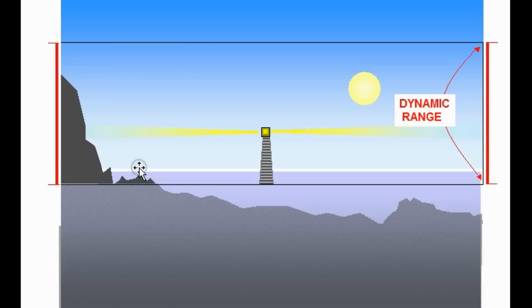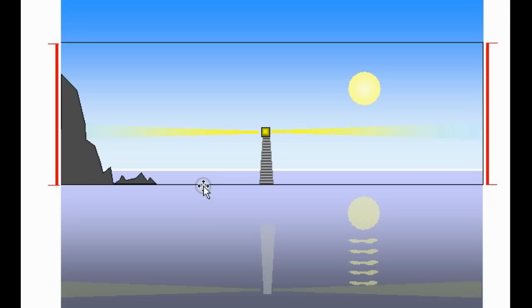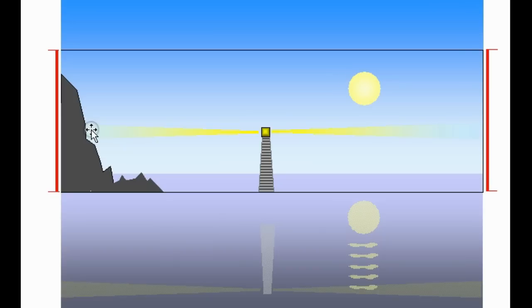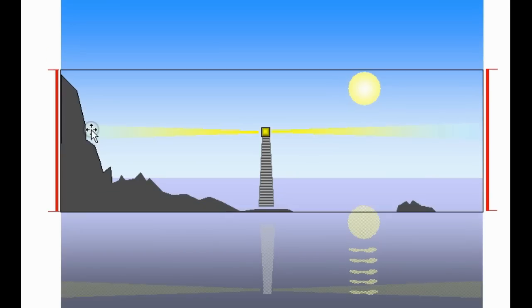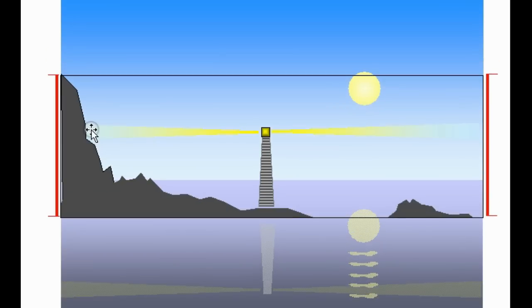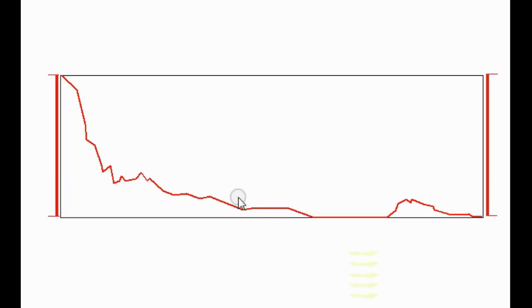Now the current setting, our spectrum would look just like this. So much of the lower level signals is lost from view. Going back to our ocean view, we can now reduce the level of water. This is the same as reducing the amount of attenuation. It makes our analyzer more sensitive. If we look at the spectrum now, it would look like this. Whereas before, with maximum attenuation, we saw this, where much of the lower level signal was lost to view.